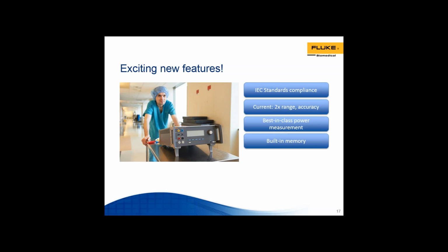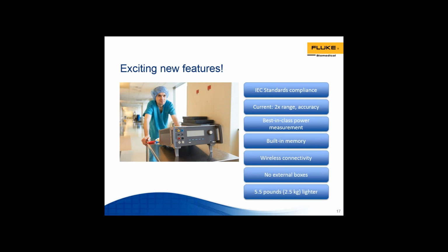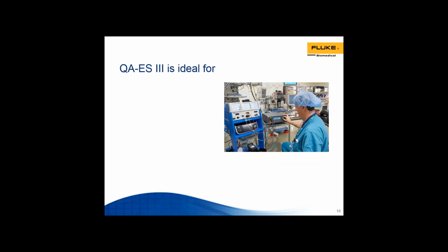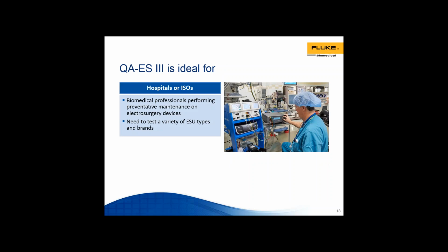It features built-in memory, so you can record everything on the analyzer for easy retrieval later. And this data retrieval can be done either through a wired USB interface or wirelessly. And finally, we have gotten rid of all the external boxes, which added cost and complexity. So there are no external boxes needed. Everything that you need is built into the analyzer. And while doing all of that, we've shaved off about 5.5 pounds or 2.5 kgs, which makes this product exceptionally light compared to its predecessor. The QAES3 is ideal for anyone working within a hospital or ISO performing preventative maintenance on electrosurgical devices. Anybody that needs to test a variety of ESUs in terms of types or brands, because this product is compatible with multiple brands and types of ESUs.